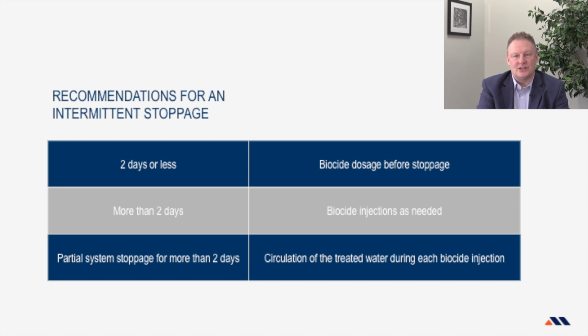As a rule of thumb, for stoppages of 2 days or less, there should be no problem as long as the biocide is injected before the stoppage. When the outage is longer than 2 days, it is recommended to inject biocides at regular intervals as required and ensure that it is dispersed throughout the entire system. It's important that the recirculation pumps be restarted during the injection of the biocide to maintain circulation and to ensure an even concentration throughout the system.